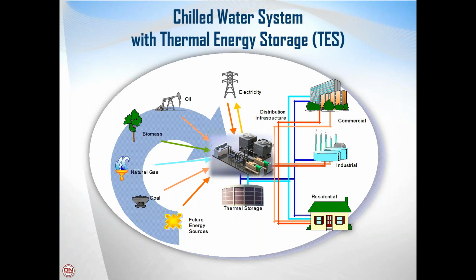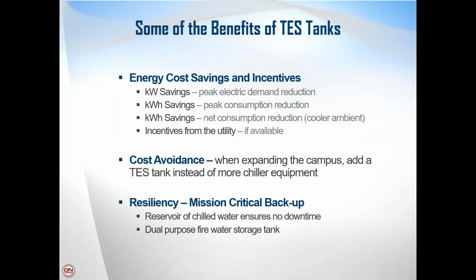The tank can be added to that system, and it acts like a virtual battery. It allows the owner or the operator to run their very high horsepower equipment, the chillers, the pumps, the cooling towers, when it's most beneficial to them. Typically, that's during off-peak hours or nighttime when it's cooler ambient conditions outside and a lower cost of power. They can run that equipment. They can store water in that tank, and then during the daytime, utilize that cold water that's been stored in the tank for cooling their building or their campus.